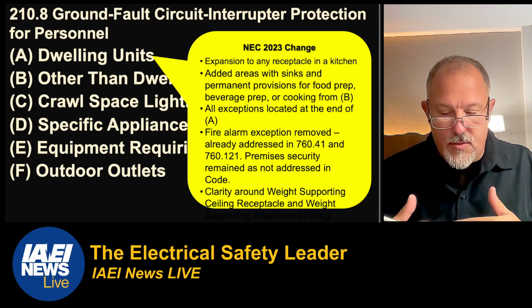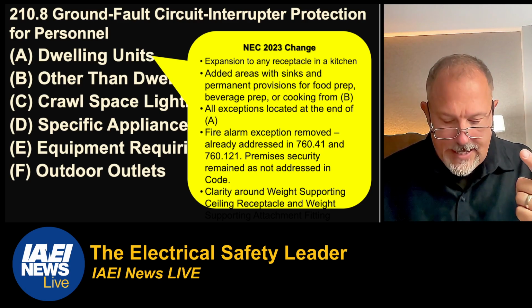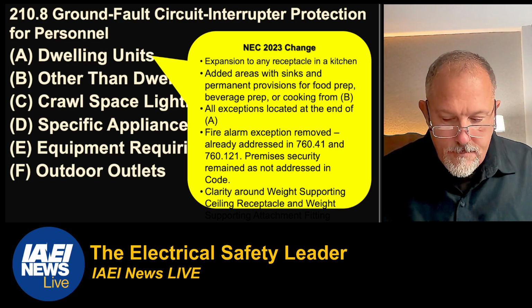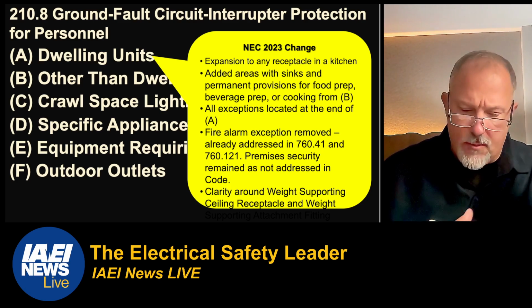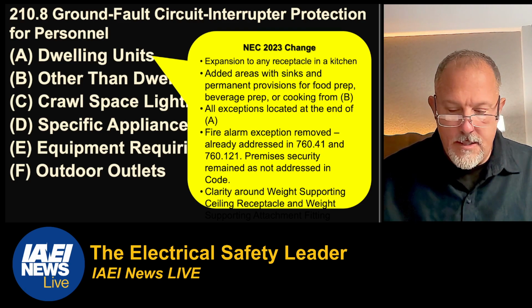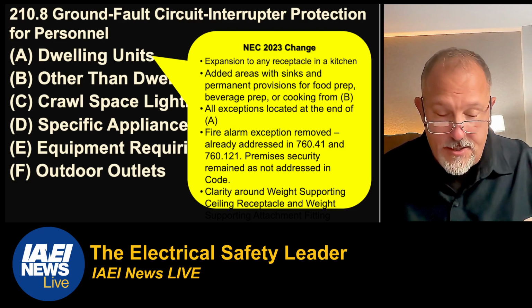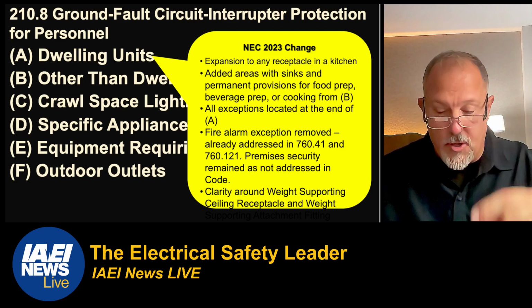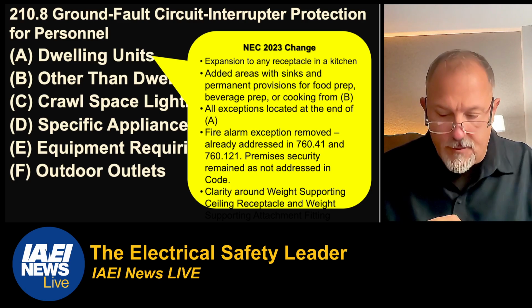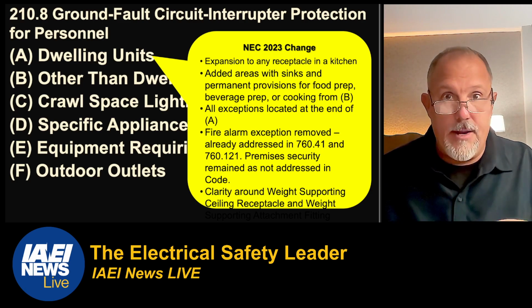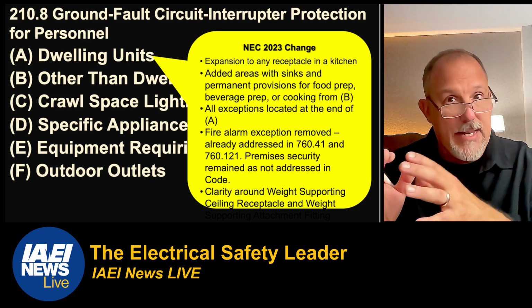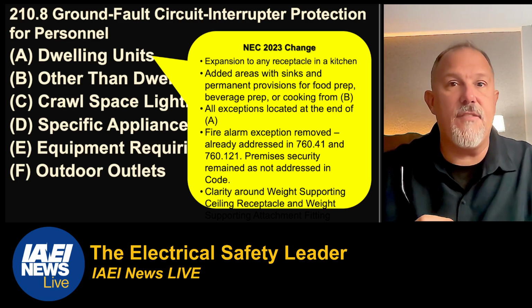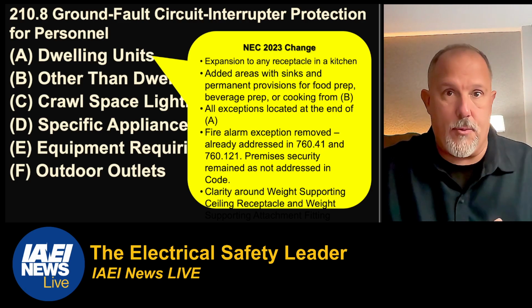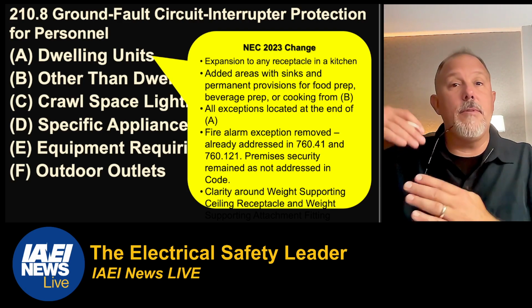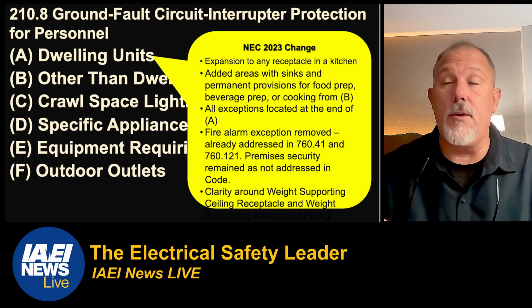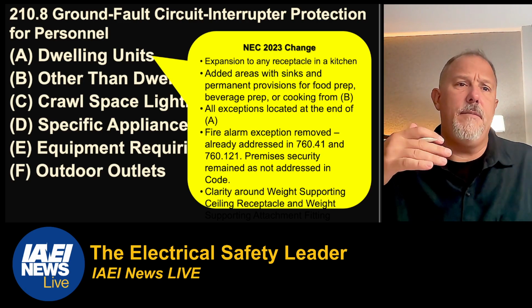Then what we did was we took the language, if you remember, in 210.8(B). In 210.8(B) last cycle, I believe it was last cycle, we said, in addition to kitchens, we had areas with sinks and permanent provisions for food preparation, beverage preparation, or cooking. And it was the "or cooking" and not the "and cooking" that gets you out of saying it's a kitchen. So you may not have cooking provisions, but you have food preparation. And that was a key in to say you need to GFCI protect. And the target there really were like those Starbucks stations and similar.